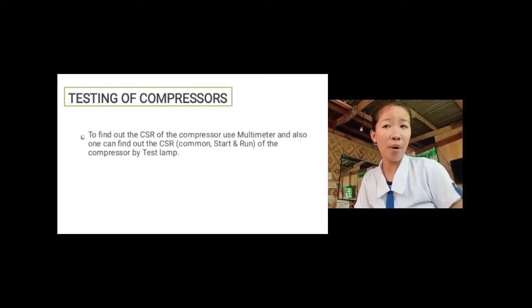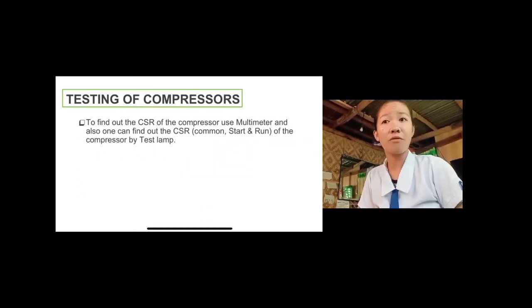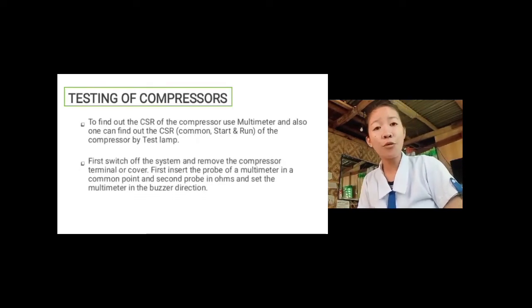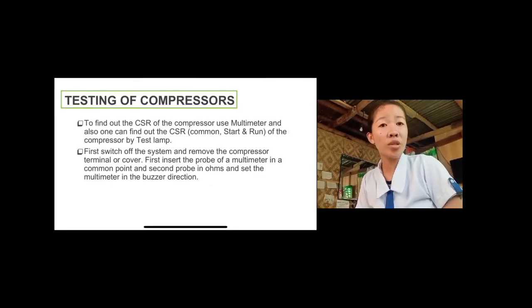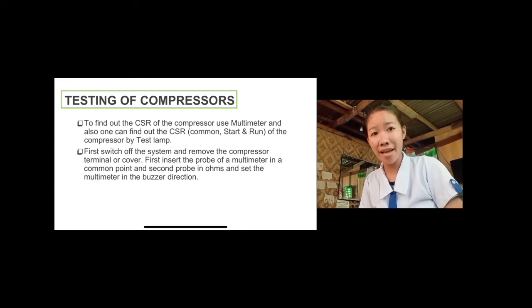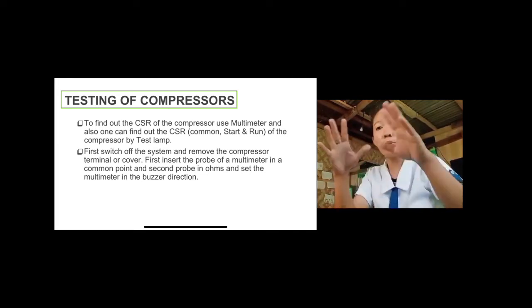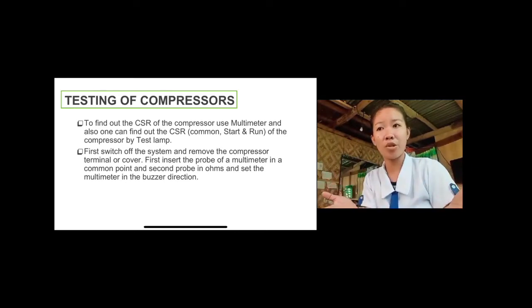When testing compressors to find out the CSR of the compressor, use a multimeter, and you can also find out the CSR of the compressor by test lamp. First, we use the multimeter to find the CSR of the compressor. Next, first switch off the system and remove the compressor terminal cover. So we first switch off the operating system and remove the cover of the compressor.